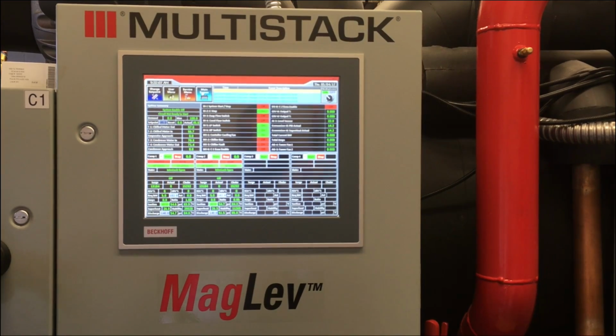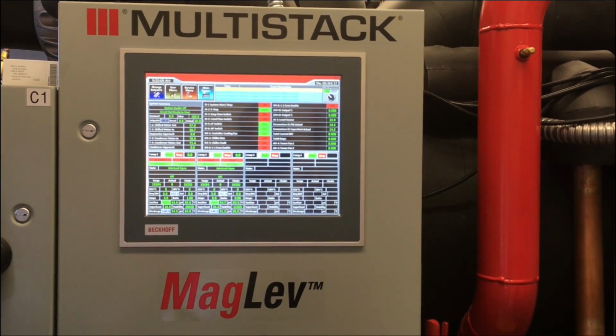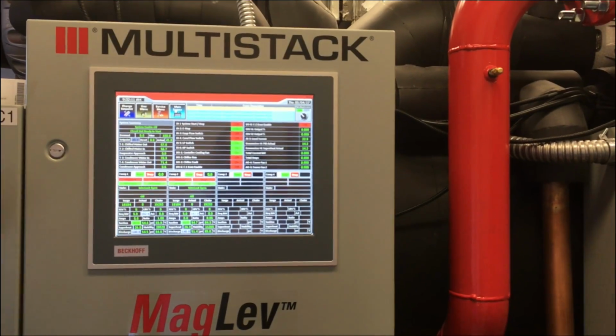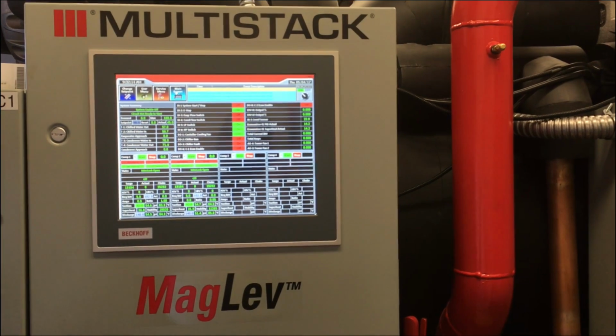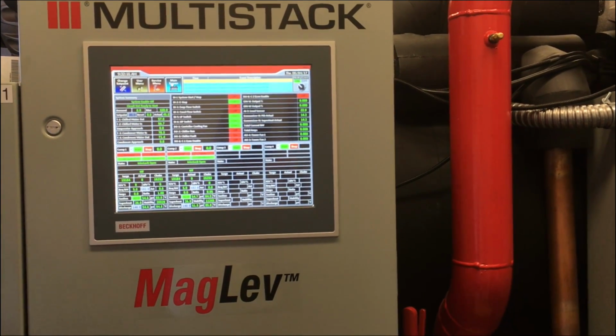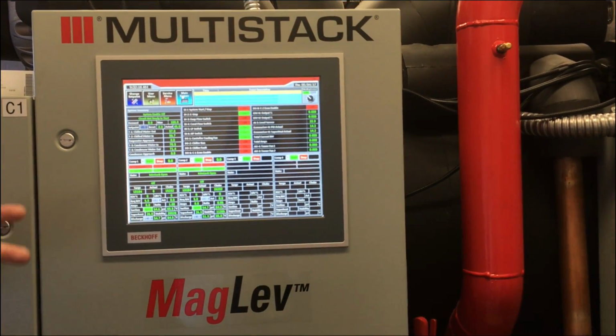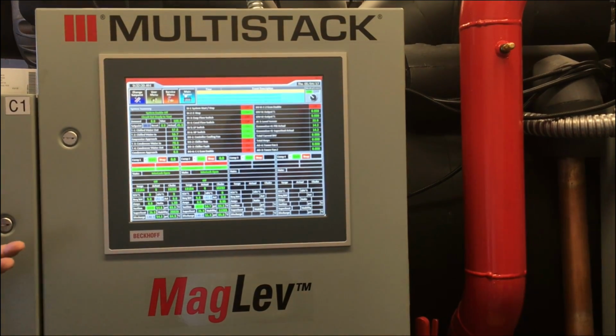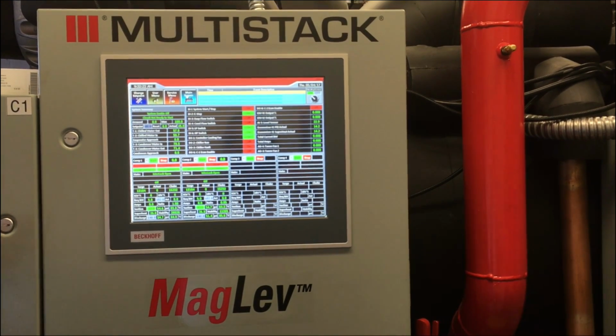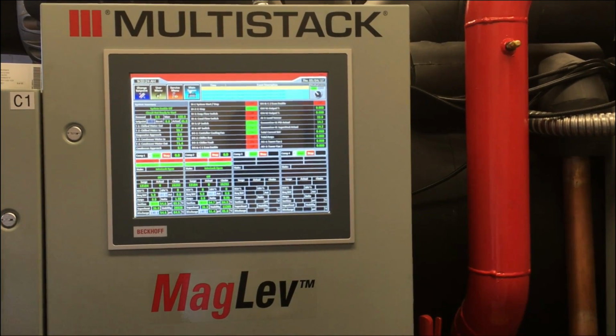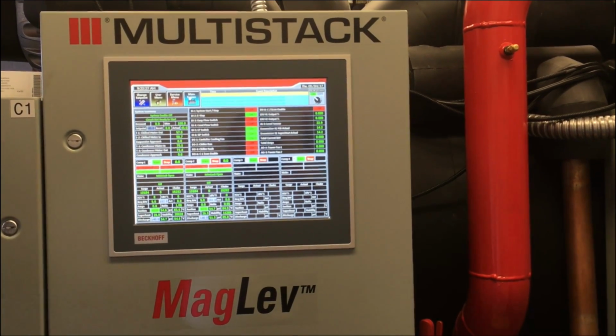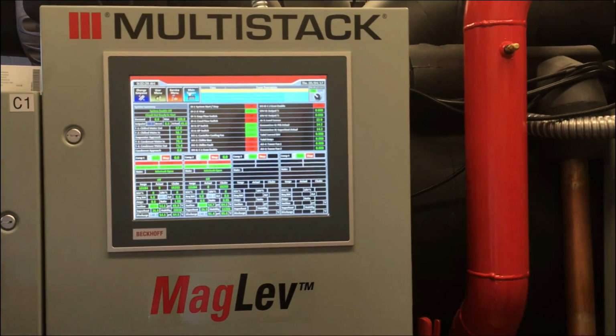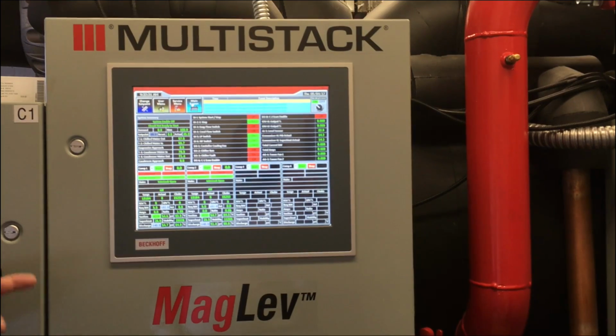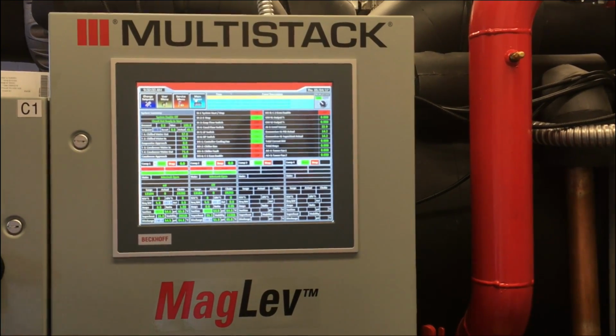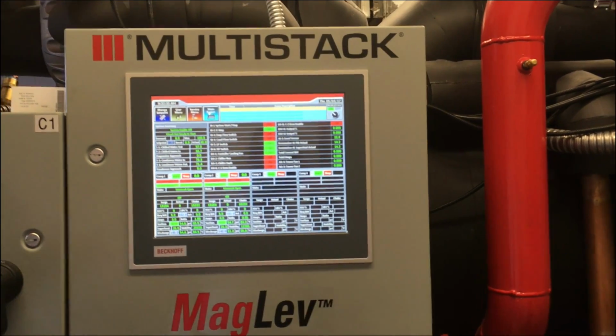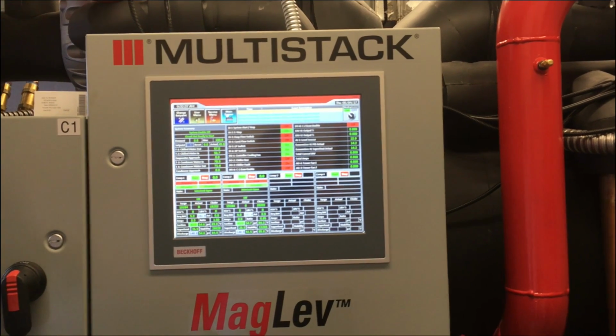If the power goes away for any reason at all, it spits out a fault condition on its way down. Just to say my 670 volts DC is now under 500 and I can't run, so I'm going to spit you an alarm to let you know that I can't run. So it comes out as bearing motor fault, and then everybody thinks the sky is falling because it sounds devastating, and it's not. So if you get 3 alarms of the same in a half hour, this compressor will lock out. So if you get 3 bearing motor faults on power fail is the only one that doesn't, because technically it refreshes itself every time you restart.